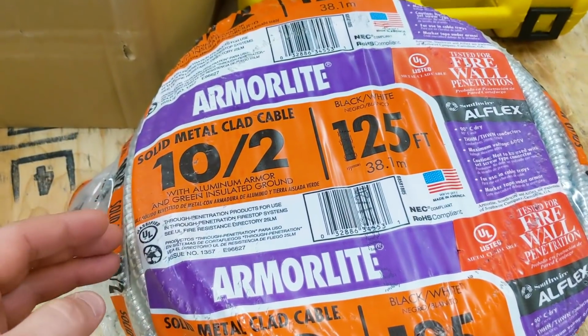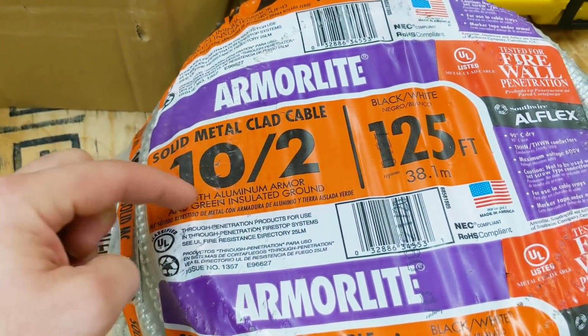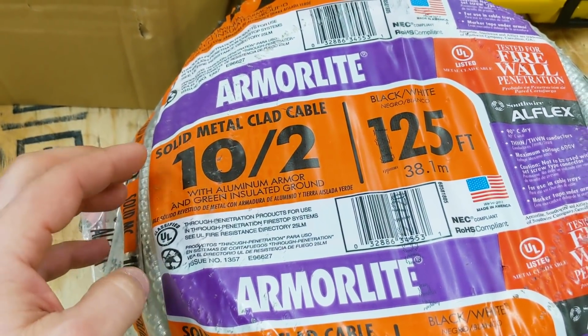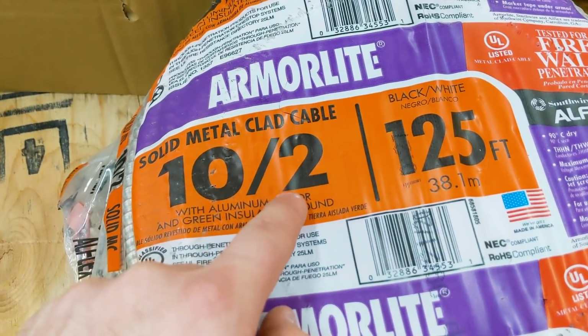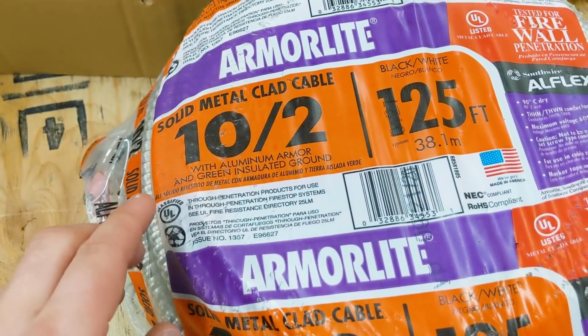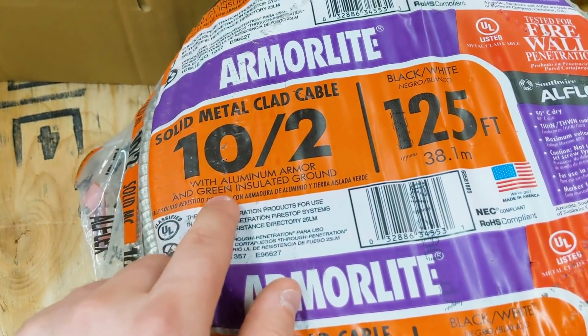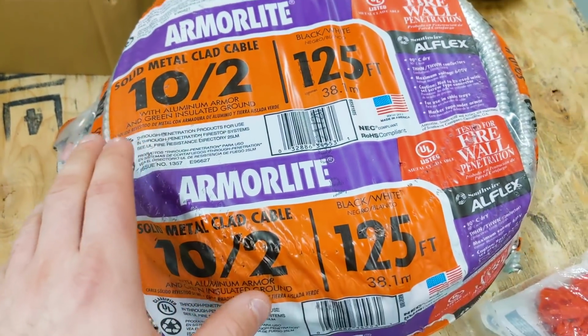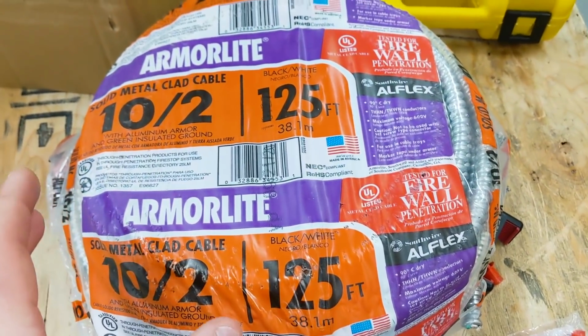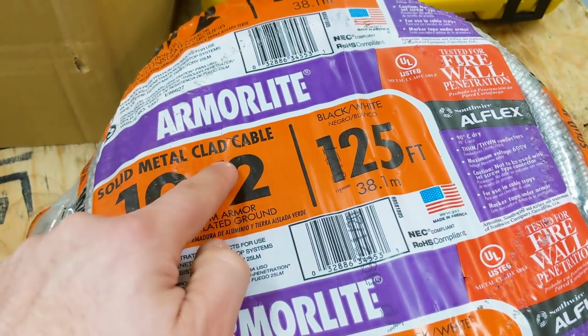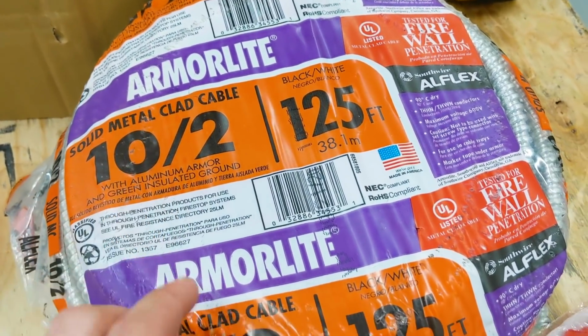The water heater needs to be run with 10 gauge wire, because it's on a 30 amp circuit breaker. The 2 means 2 current carrying conductors inside, plus a green insulated ground, so there are actually 3 wires inside, one of them being a ground. This is metal clad, which is why we call it MC.